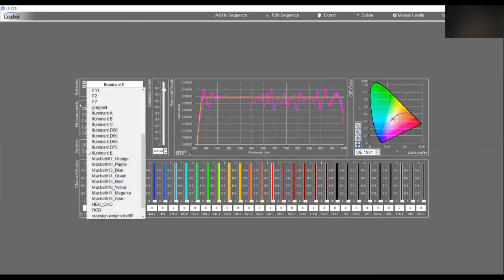And then when you execute it, it's going to walk you through the process. It's going to turn on the tungsten halogen light source. It's going to let you know when it's stable, and then it's going to run through the calibration process. And when it's done, now your spectroradiometer has a new calibration factor. And you'd be all set to go.